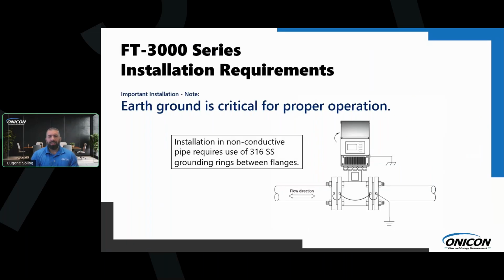When talking about installation with these meters, grounding is critical for any and all electromag meters. This is our insertion meters as well as our inline mag meters. It's a little bit easier with our mag meters to ground. So this is an example of a conductive pipe. So this is your coppers, your steels. We still need the flanges to be bonded together. So we do require it to be drilled and tapped on the pipe flange, and we have the grounding lugs on our flanges.